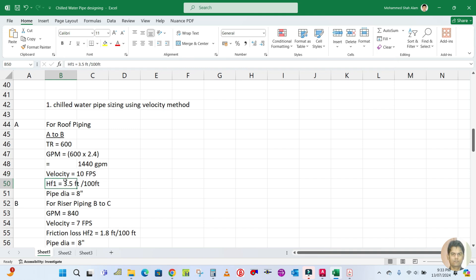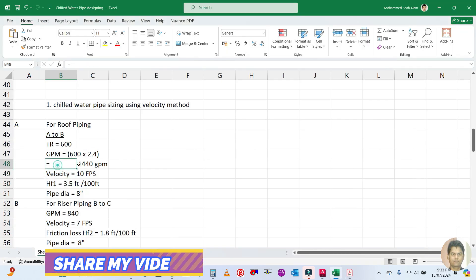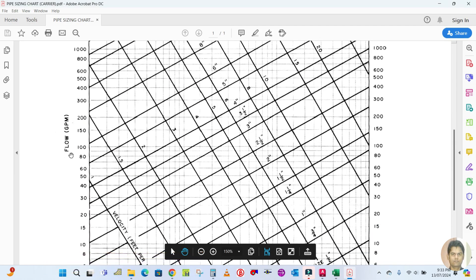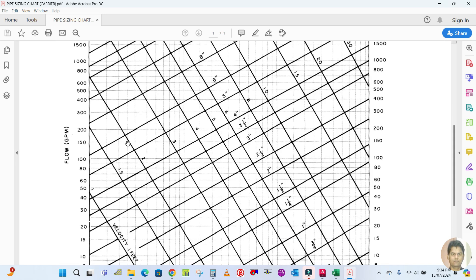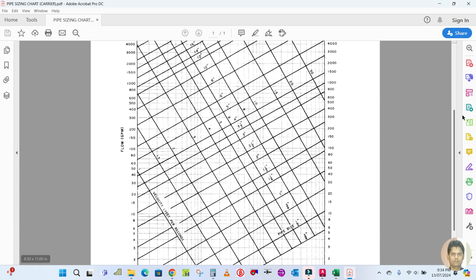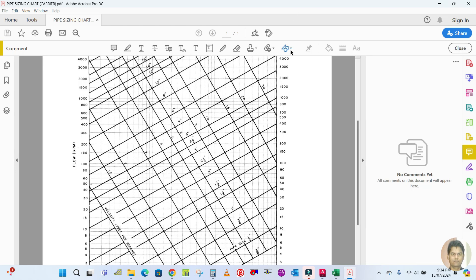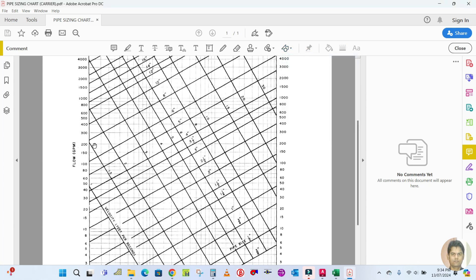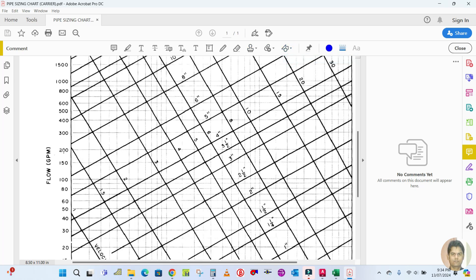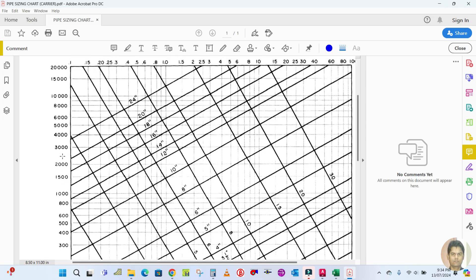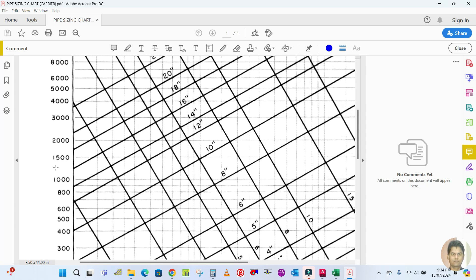We now calculate HF1, the friction loss, using the chart with two values: flow rate and velocity. On this chart, the Y-axis is flow rate in GPM. Our GPM is 1440 — that's close to 1500 on the chart — so I'll draw a horizontal line at approximately 1440 GPM.